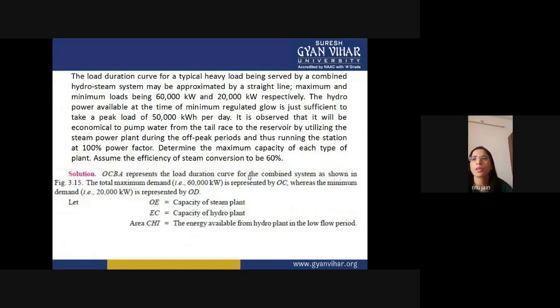Now this is a very important question, so we will discuss this numerical. The problem is given that the load duration curve for a typical heavy load being served by a combined hydro steam system, so hydro is also connected and the steam power plant is also connected, may be approximated by a straight line, with maximum and minimum loads being 60,000 kilowatt and 20,000 kilowatt respectively. So the maximum load of this hydro and steam system is 60,000 kilowatt, and the minimum load is 20,000 kilowatt.